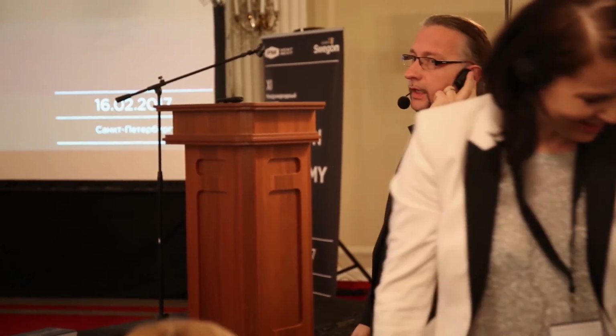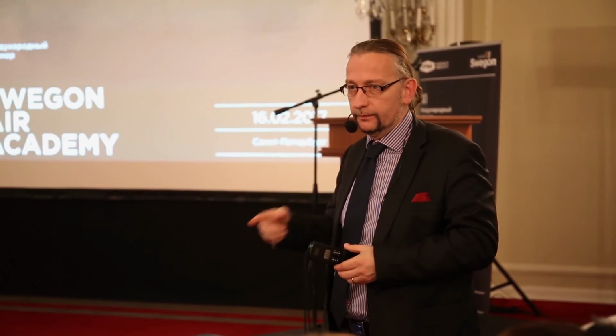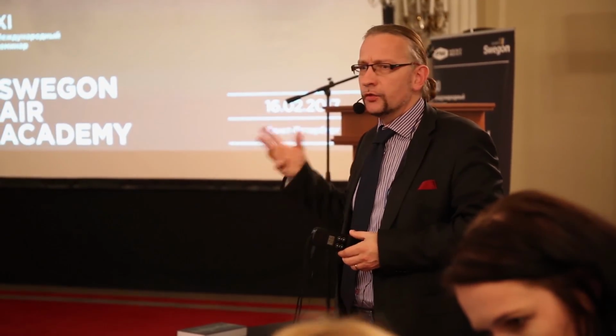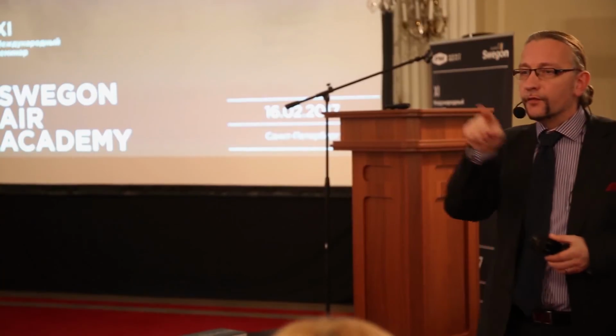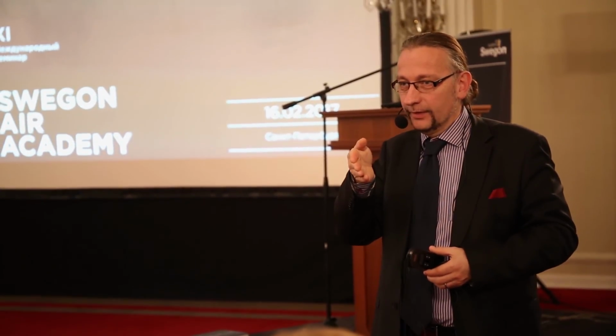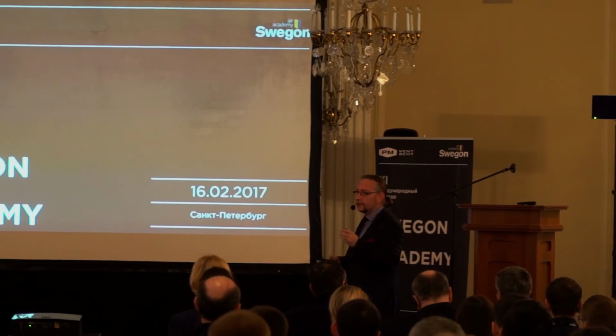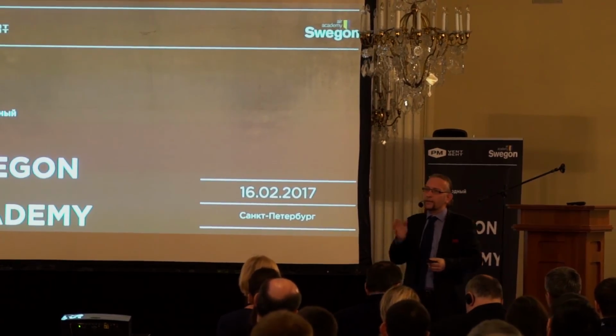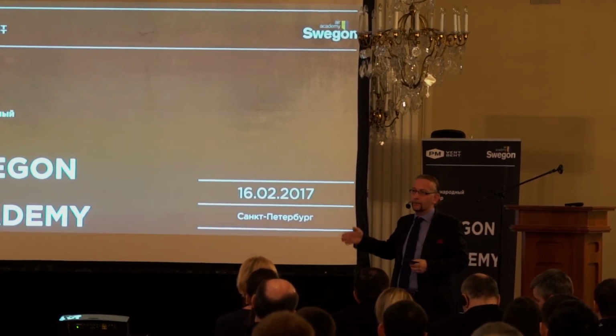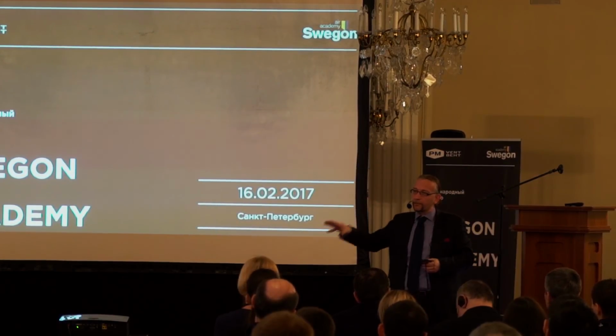Right. Now, again, for the hotel rooms, the rule of thumb that you should remember is when the room is occupied, it should be around 80 cubic meters per hour of air change. Right? That is about 22 liters per second. Okay? When the room is unoccupied, it should be around 40, about half. Okay? So that already saves a lot of energy. It should not be 0. It should be 40. And 40 means 40 out from the bathroom and 40 into the hotel room.